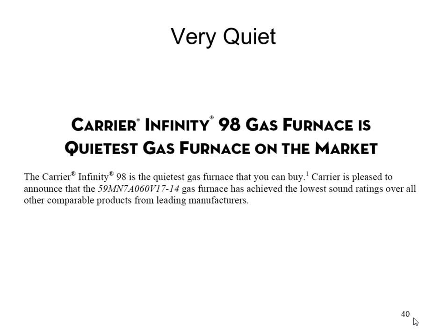It's basically a 4-wire communicating stat, and instead of a regular stat that says I want 1-stage heat or I want 1-stage cooling, which is what a normal stat does, this guy says I want 72 degrees and my current temperature is 71.3. And then the furnace looks at that and says you want 72 and it's 71.3, so you want 0.7 of a degree of heat. Great. It'll modulate to try to maintain that. And then it'll track how fast you're getting to that 72, and it'll quote-unquote speed up the gas valve or slow it down to get you there at the right time.